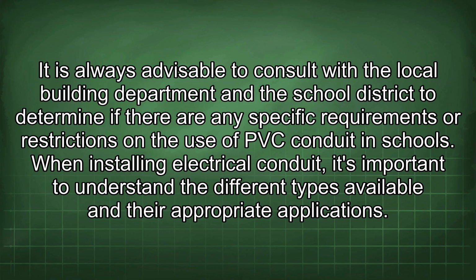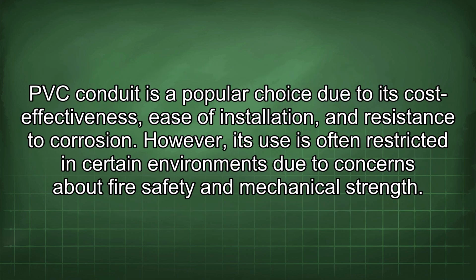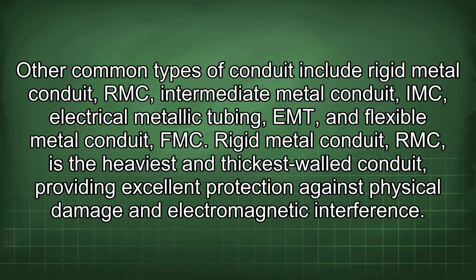When installing electrical conduit, it's important to understand the different types available and their appropriate applications. PVC conduit is a popular choice due to its cost-effectiveness, ease of installation, and resistance to corrosion. However, its use is often restricted in certain environments due to concerns about fire safety and mechanical strength.